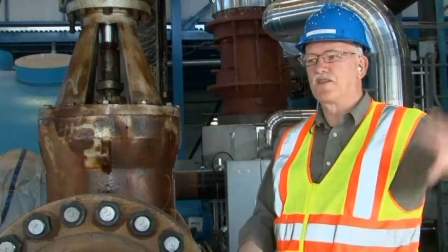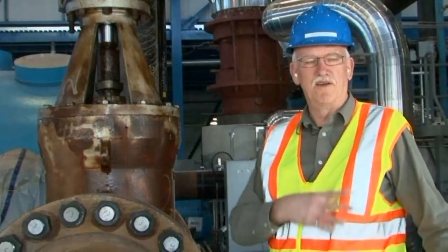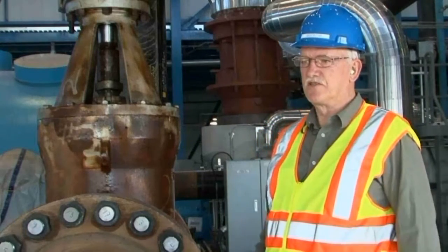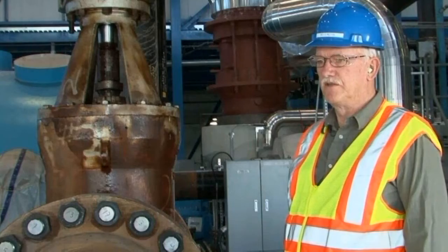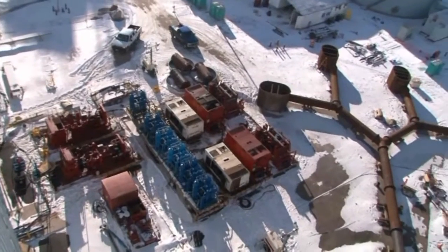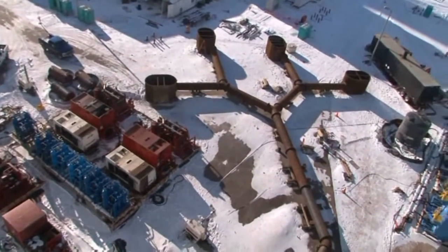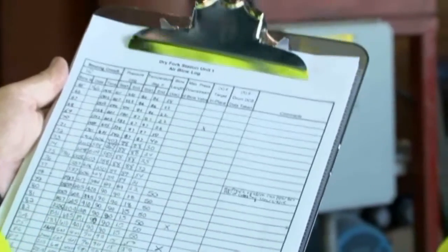So it's to get all that debris out. There might even be stuff that's left in there like a bolt or something like that that will get cleaned out of the system. Doug Rothy is the mechanical performance consulting engineer on site. The last time he oversaw air blows was on Unit 2 of Antelope Valley Station in 1986. We used to just blow it out the side of the wall and up in the air, but now they diffuse it into these exhausters to kind of dissipate the energy, and it's safer and there's less debris flying around all over. Operations Superintendent Joel Dingman says the pipes will get air blown through them 24 hours a day, once an hour, for about 2 weeks.